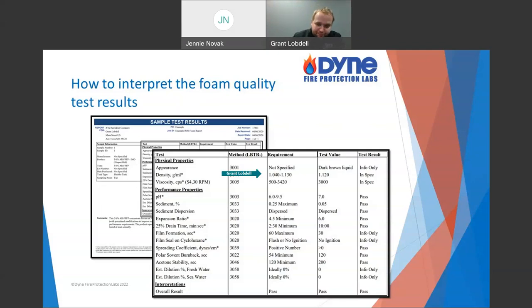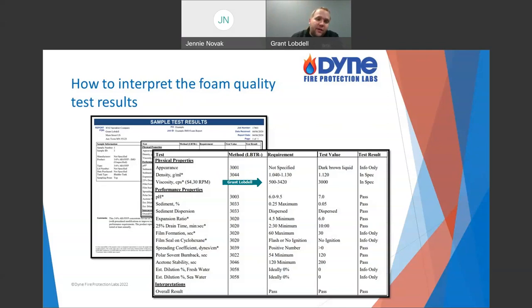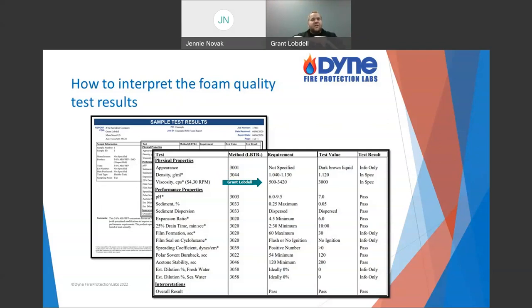Viscosity is especially important for alcohol-resistant foams, which have thickness to them. Why are they thick? There's a thick polymer ingredient added to make them alcohol-resistant. When the foam is on top of an alcohol, that polymer is designed to fall out of solution, sit on top of the alcohol — kind of like a film — and protect the foam blanket. So that polymer providing protection against alcohol is also what gives us the thickness.